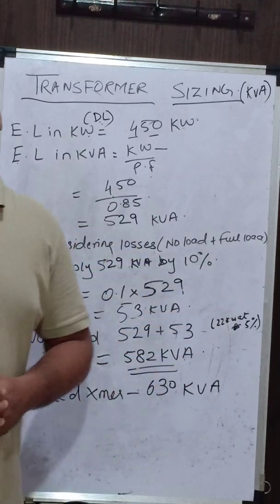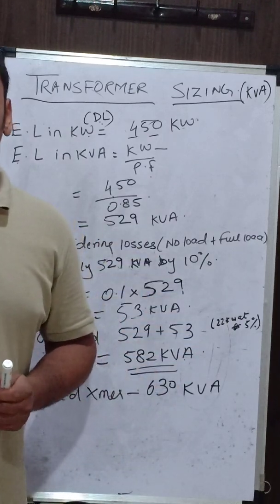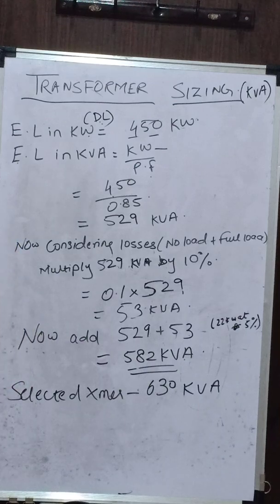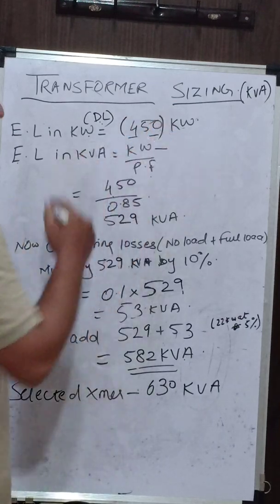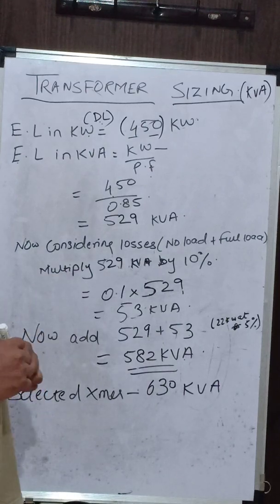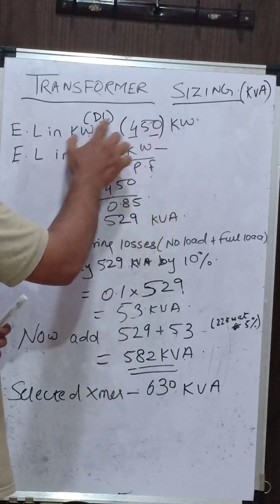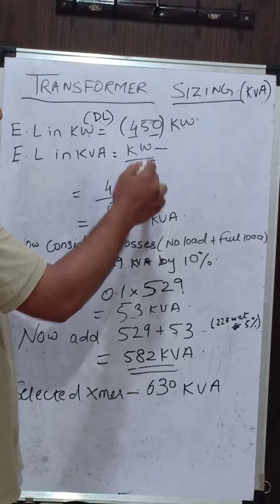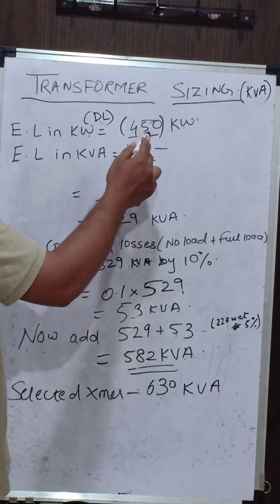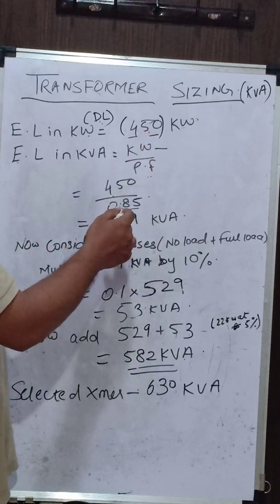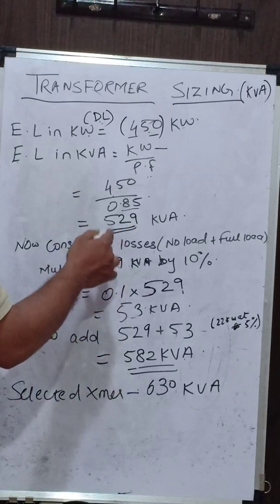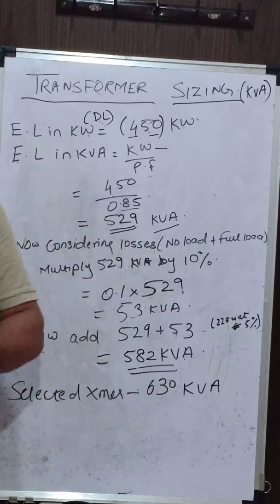The final electrical load should be a demand load, not a connected load. Based on the calculated demand load — say we reach a value of 450 kilowatt for the residential building — we first need to convert this kilowatt into kVA. To convert kilowatt to kVA, divide kilowatt by the power factor. Dividing 450 kW by a power factor of 0.85 (at the transformer side), the total kVA comes out to 529 kVA. This is your demand kVA — the requirement of all electrical loads in the building.